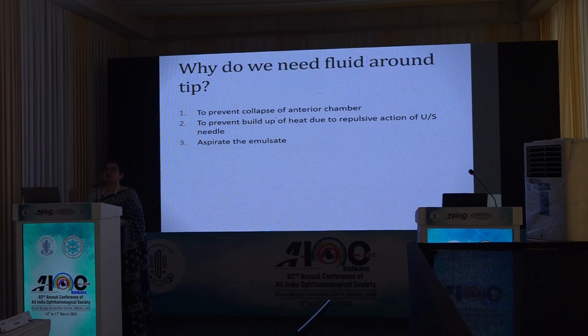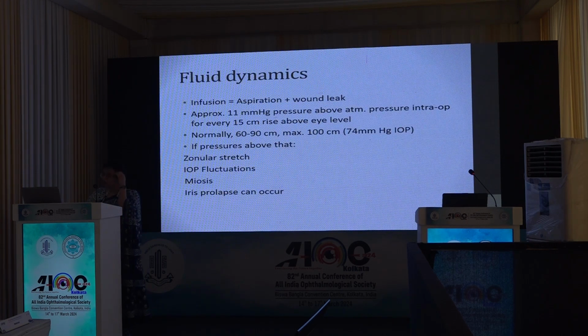So to counteract the heat which is generated, we need fluid around the tip. It is to prevent the collapse of the anterior chamber, also to prevent the buildup of heat, and also to aspirate the emulsate. Now what are the fluid dynamics? Infusion is equal to the aspiration, the fluid which comes in, and also the wound leak. So we have to maintain a stable anterior chamber, both should be balanced.